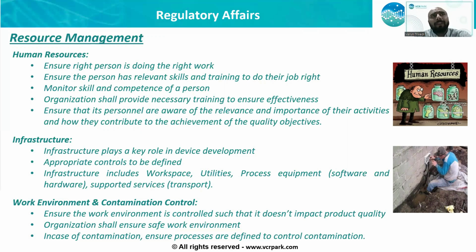From human resource, we then look into the next resource activity, which is the infrastructure. When we talk about infrastructure, we are looking at everything from the workspace to the different tools to even the transportation that you might be using to ship your device from one place to another. All of this is something that we need to keep in control, keeping in mind the overall development activities for the medical device. For example, if you are into the field of optics and you're developing something like an optical camera for imaging, say, your retina, you need to ensure that the overall production facility is clean, even to the extent that you are doing it in a clean room. So your overall infrastructure shall be accordingly maintained and managed.